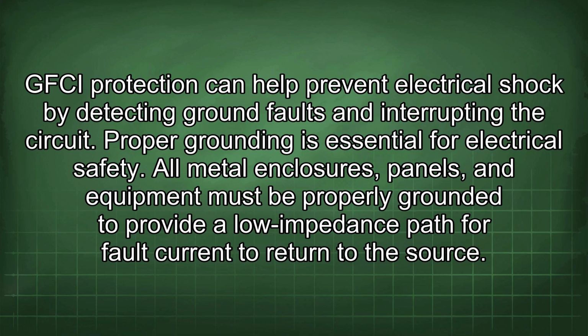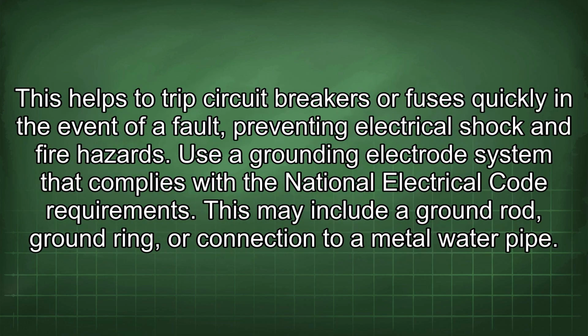All metal enclosures, panels, and equipment must be properly grounded to provide a low impedance path for fault current to return to the source. This helps to trip circuit breakers or fuses quickly in the event of a fault, preventing electrical shock and fire hazards.